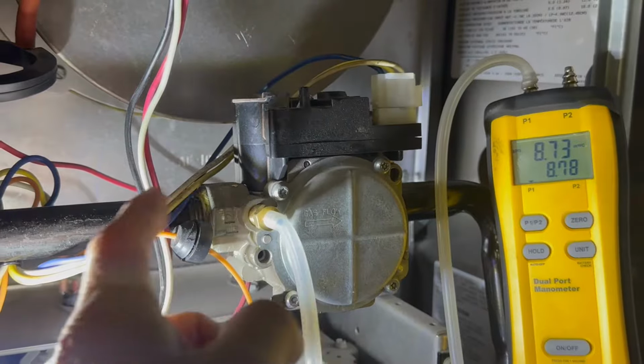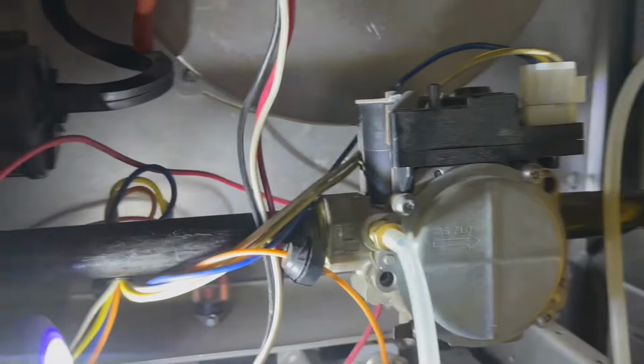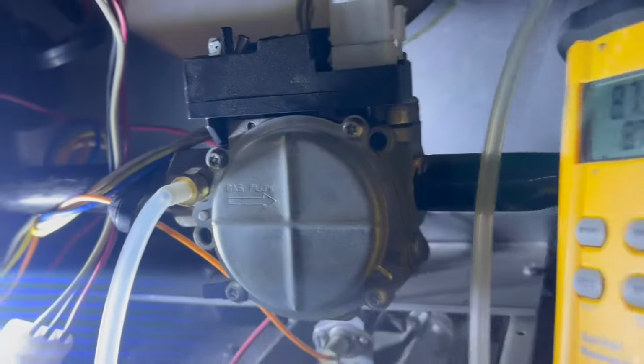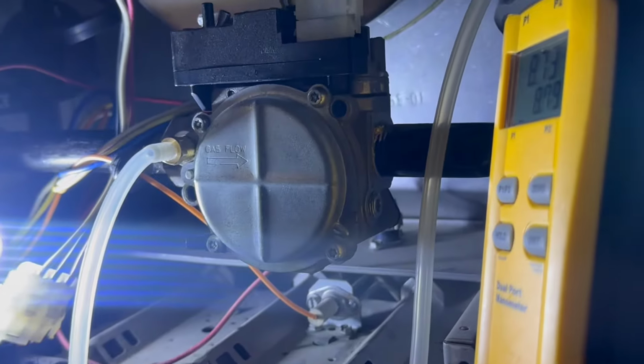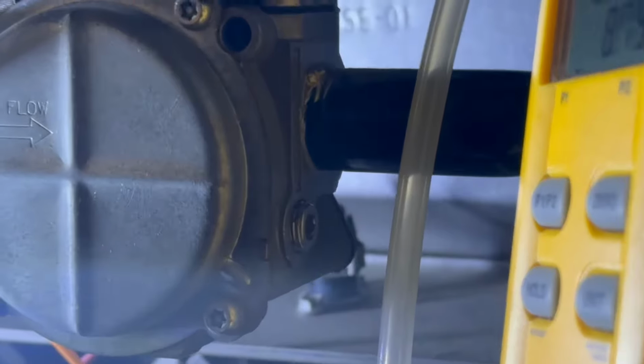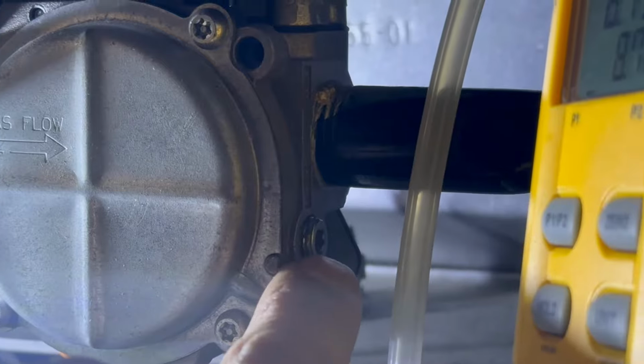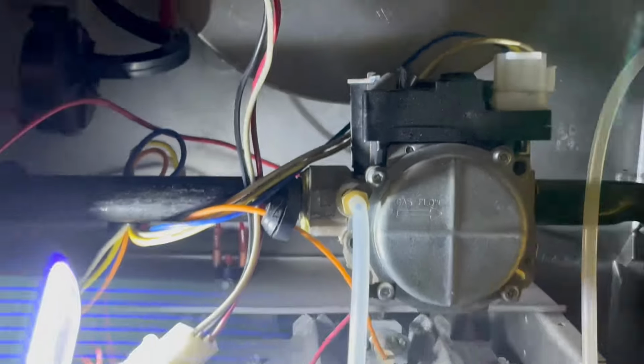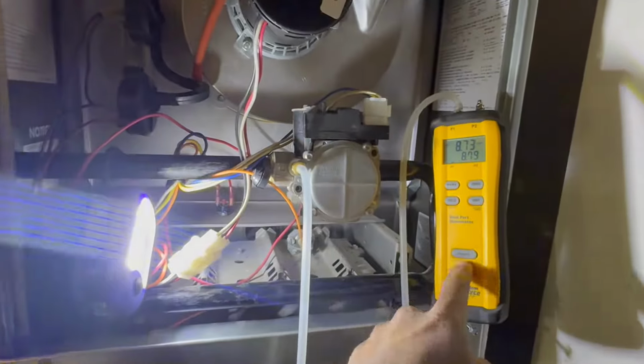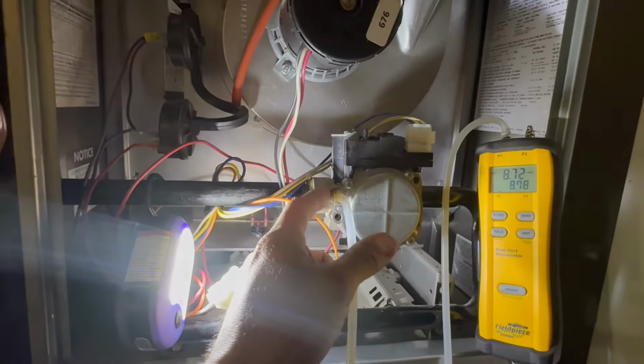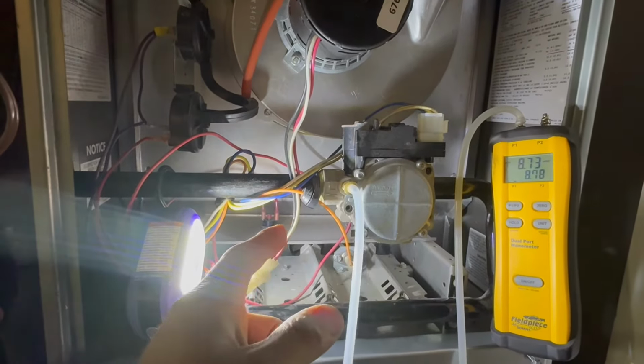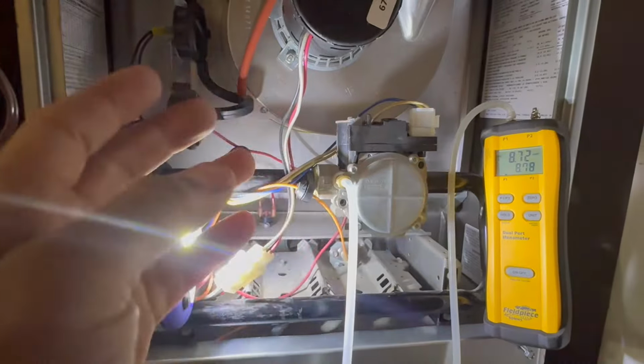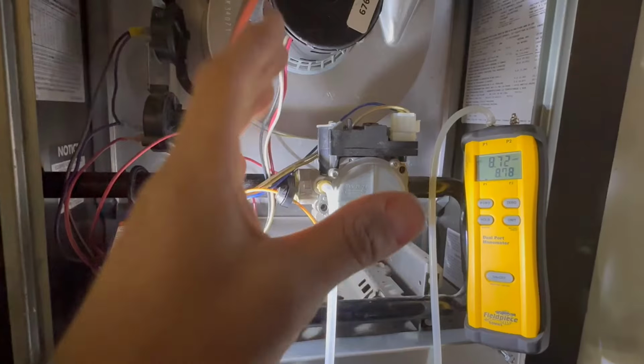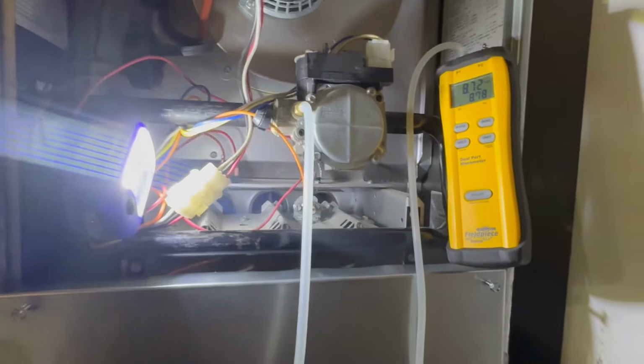We're just gonna check if we have pressure coming in here, and then the other one, the outlet one, is right there. Let's see if you can see it. Let's see if I can zoom in. You see, it's right there. So yes, to be able to read this properly, you do need the manometer, you need the tubing, you need the little adapter to fit in, but that's about it. That's all you need to be able to read gas pressure from this gas valve.